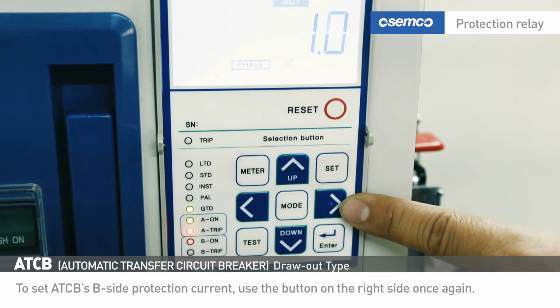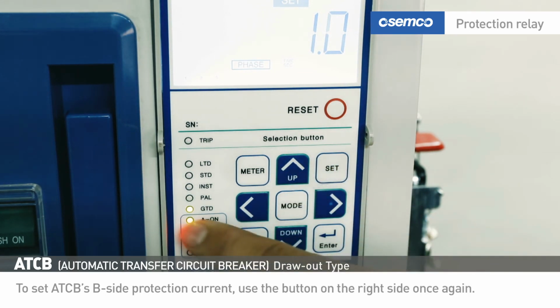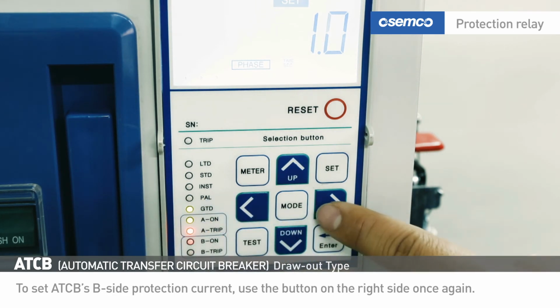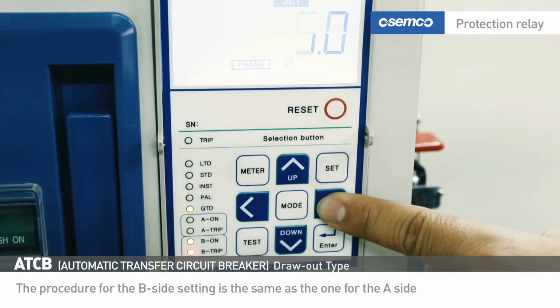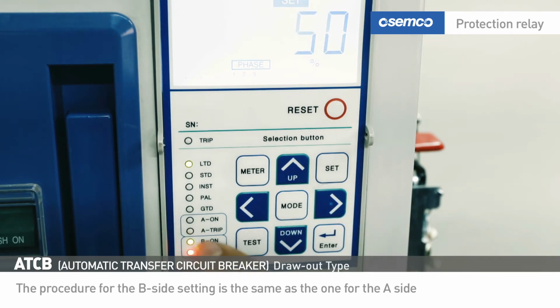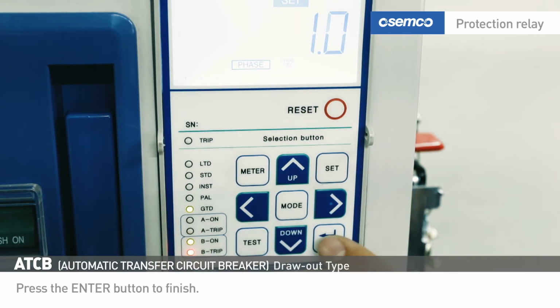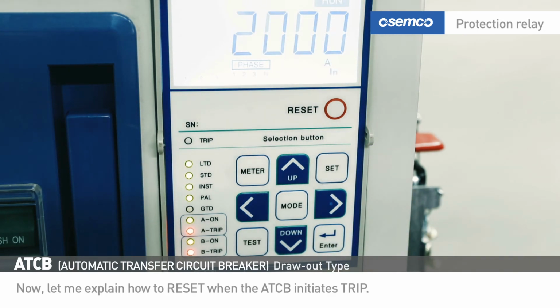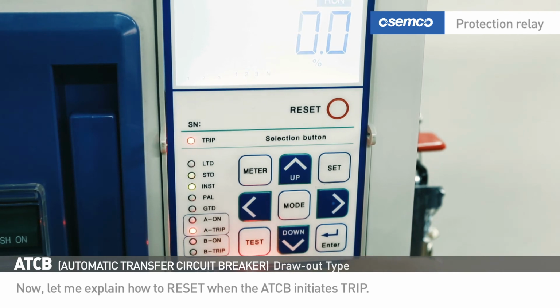To set ATCB's B-side protection current, use the button on the right side once again. The procedure for the B-side setting is the same as the one for the A-side. Press the Enter button to finish. Now, let me explain how to reset when the ATCB initiates trip.